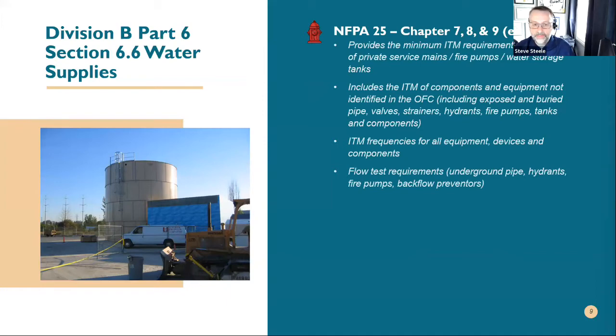Flow test requirements: underground pipe, hydrants, fire pumps, backflow preventers. A couple of things to note, two things that will come up, especially in the province of Ontario. Backflow preventers being one, because of municipal regulations or requirements for inspection, testing, and maintenance. You have two requirements now. Once you get NFPA 25 as a standard or enforceable under the fire code in the province, you now have two regulatory bodies looking at requirements. So a backflow test, an annual test done by or as required by the municipality, done through OMFPOA and so forth, does not meet all the requirements of NFPA 25 or the fire system.